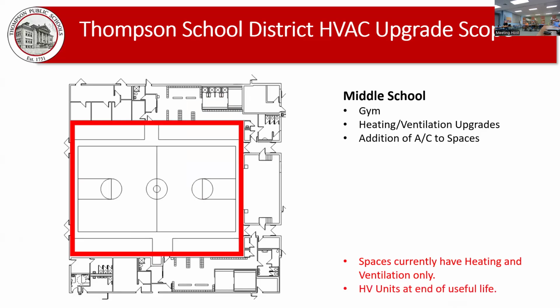For the middle school gym, there are currently two ceiling-hung units, one over each end of the stands area. This one sounds like it's going to fall apart any minute. Not sure what's going on there, but it's at the end of its useful life, heating and ventilation only. The existing ductwork will remain; we'll replace the unit in kind. There's a flat roof right above here where we'd add DX on the backside. So basically it's a 1-for-1 replacement, just increasing ventilation and adding AC.